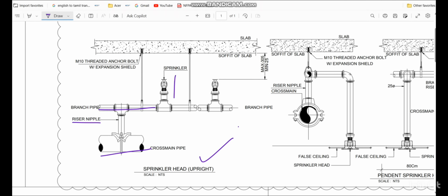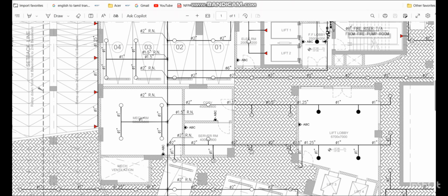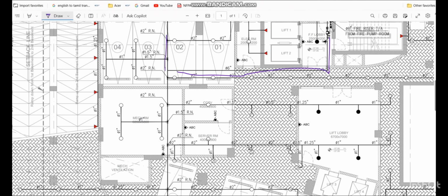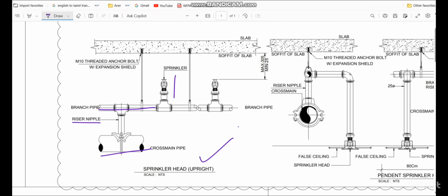This type of arrangement we normally do in the basement. For example, in the basement we saw that we have the cross main like a loop system. So this line is coming like this, connecting with the loop system. In this loop system, everywhere we take the line up, and from here we install the upright sprinkler. So this installation I showed here will exactly match the installation we indicate here. In this case you can see the distance between the deflector and the soffit or top slab should be minimum 1 inch and maximum 300 mm, or exactly 305 mm. So this should be followed in the installation. This is the first case.